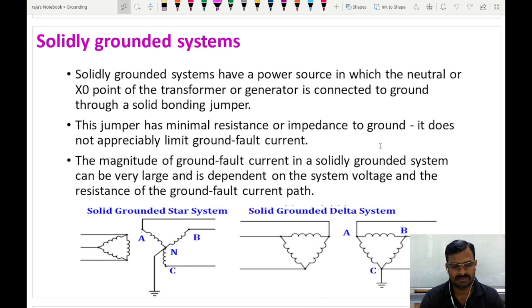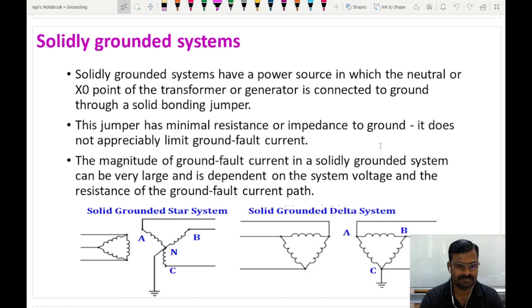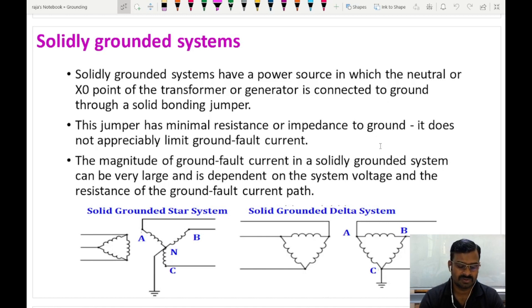What is a solidly grounded system? In an electrical power system, the generator or the transformer neutral point, if it is connected directly to the earth without any resistance using a pure conductor, this kind of earthing system is called a solidly grounded system. This conductor will have very, very less resistance so that the ground fault current will be very high.